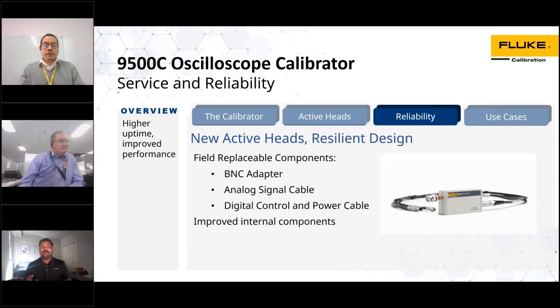The new active heads have a better, more resilient design than we've seen before. We've heard your stories of sending your 9510 heads and 9530 heads and the long times for serviceability, and the cables are always an issue, and so is the BNC connector. With the 9540 heads, the BNC adapter, the analog signal cable, and the digital control and power cable are field replaceable. This means if a cable gets worn down, an adapter gets worn down, you can replace it in your own shop. There's also improved internal components with the head itself. There's more solid state components. And the amount of relays has been reduced down to just 2 to reduce any mechanical failures within the heads themselves. Overall, the 9540 heads with the 9500C will provide higher uptime and improved performance in your calibration labs.